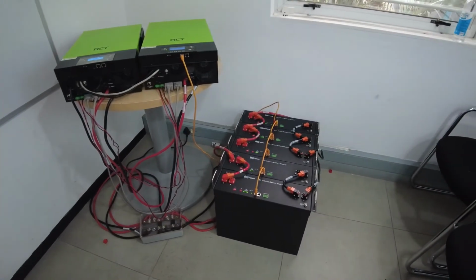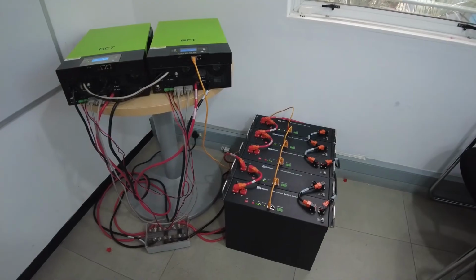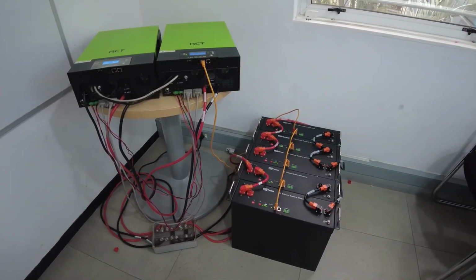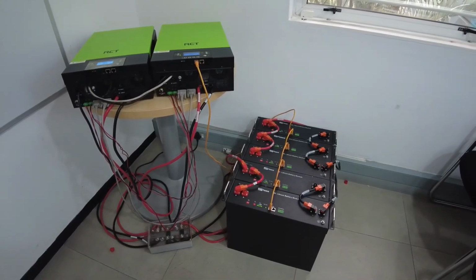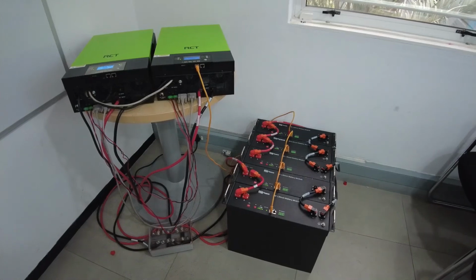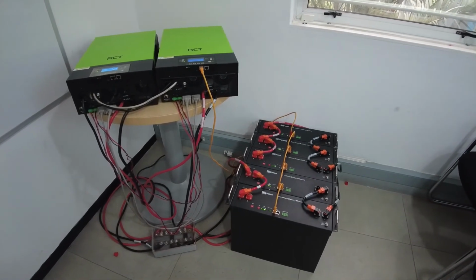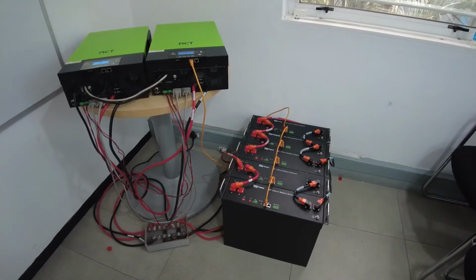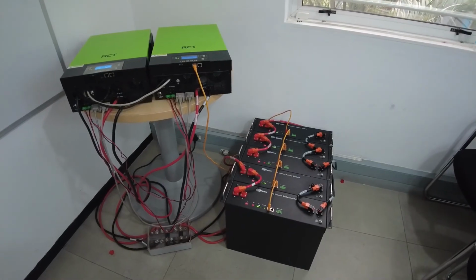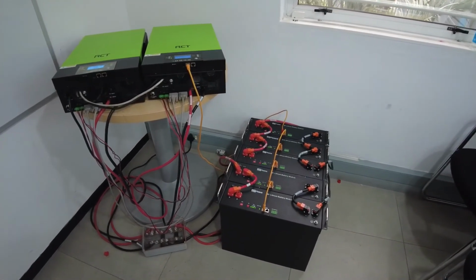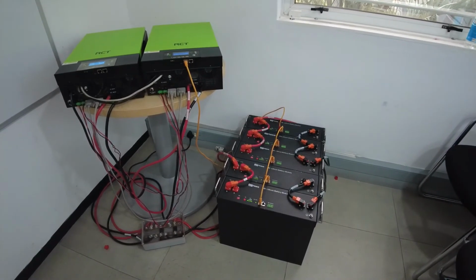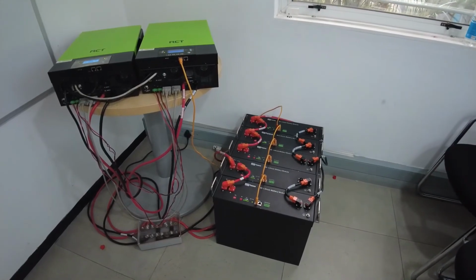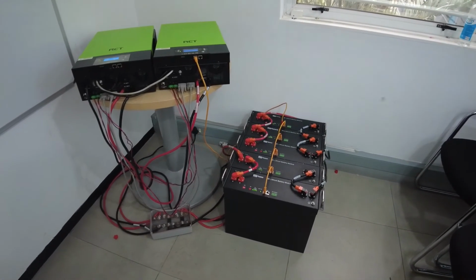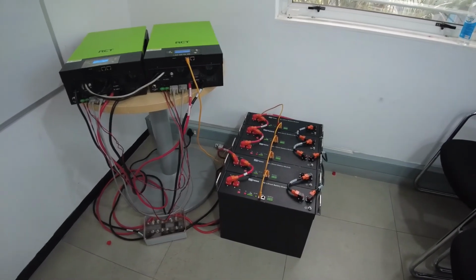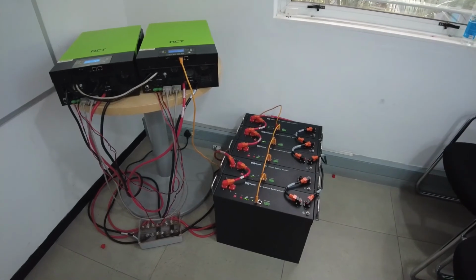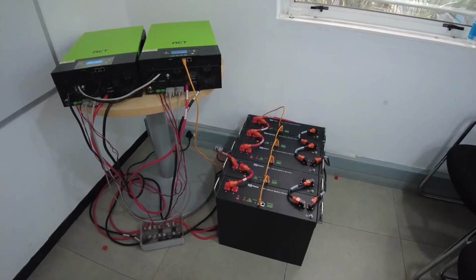For the battery BMS communication, you will notice that on the newer age Dyness batteries, I like to refer to them as the 100 series. I'm talking about the BX48100, A48100 and the BX51100. They've changed the networking port on the battery. Instead of using pins 1 and 3 as I previously mentioned, the white and orange and green and white cables, pin number 1 and 3 on the battery side, they've changed it on the 100 series to pin number 1 and 2, your 2 oranges. So you do need to rewire the BMS communication from the 100 series battery to accommodate for the inverter.